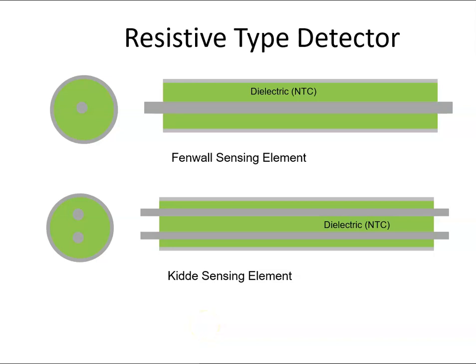Fire can also be detected using resistive type detectors. There are two that are synonymous with aviation: one is the Fenwall sensing element, the other is the Kidde sensing element, named after the two manufacturing companies. They work on the same principle but with small differences. Basically, you have a conductor in between a dielectric material, which in this case we consider as an insulator.